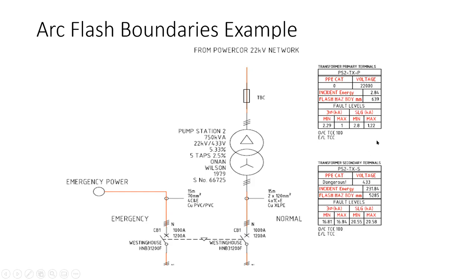But if we considered, say, Energy Safe Victoria's Blue Book on shock boundaries, we'd find that for a so-called ordinary supervised person, such as most of us are, or that's what we're considered to be, we've got to stay 2 meters clear of the high voltage and 1.5 meters clear on the low voltage. So I hope that just illustrates the point about the fact that there is no relationship between those two boundaries.